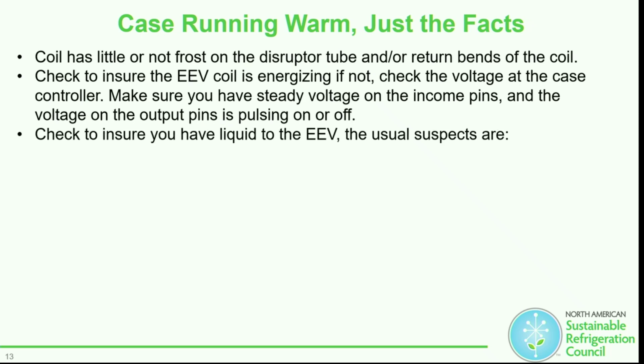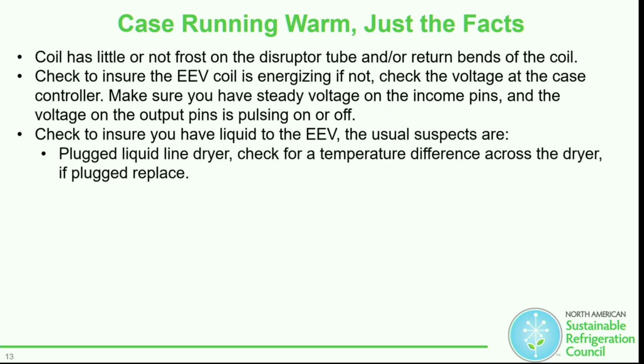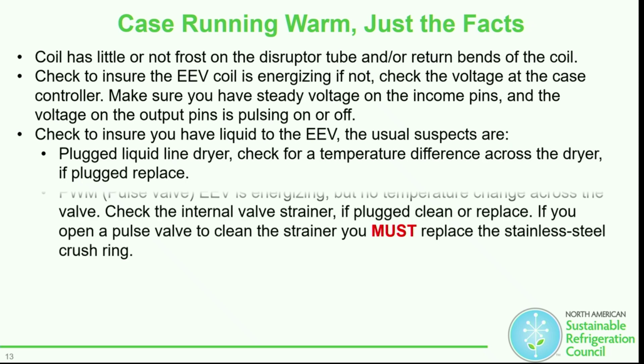Check to ensure that you have liquid to the EEV. The usual suspects are a plugged liquid line dryer. Check for a temperature difference across the filter dryer. I know with CO2 sometimes it can be difficult because you might have copious amounts of ice on the liquid line. Still check. If we have more of a temperature drop than 1 degree, I'll go with 1, that means we're flashing something off before it actually gets to the expansion device itself. Pulse width modulation.